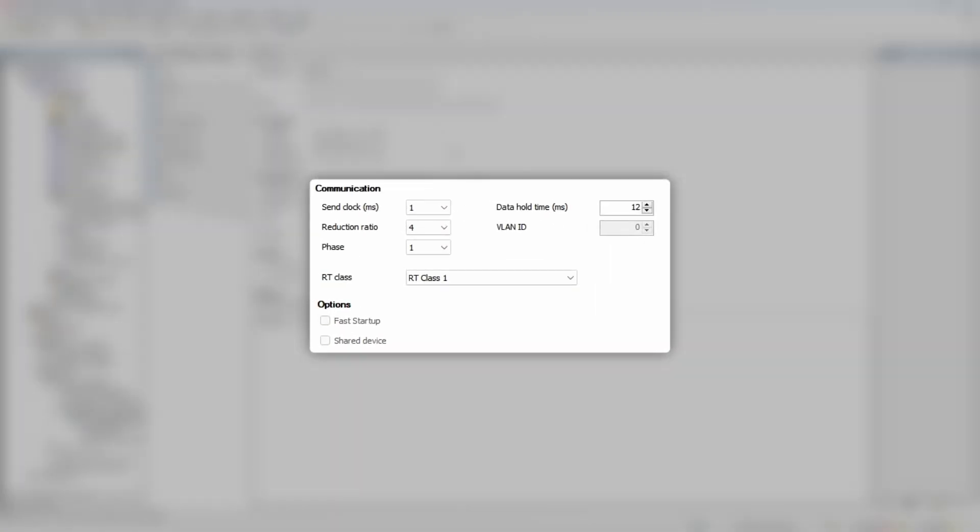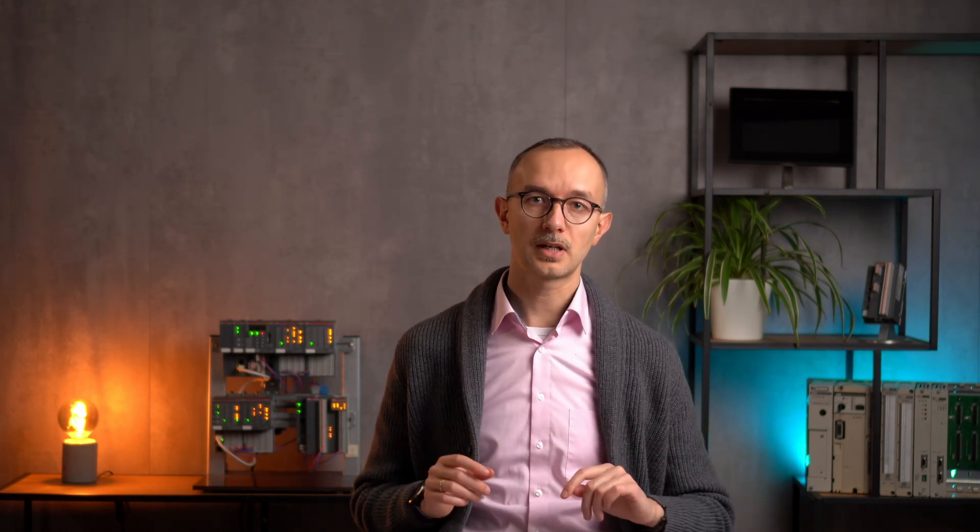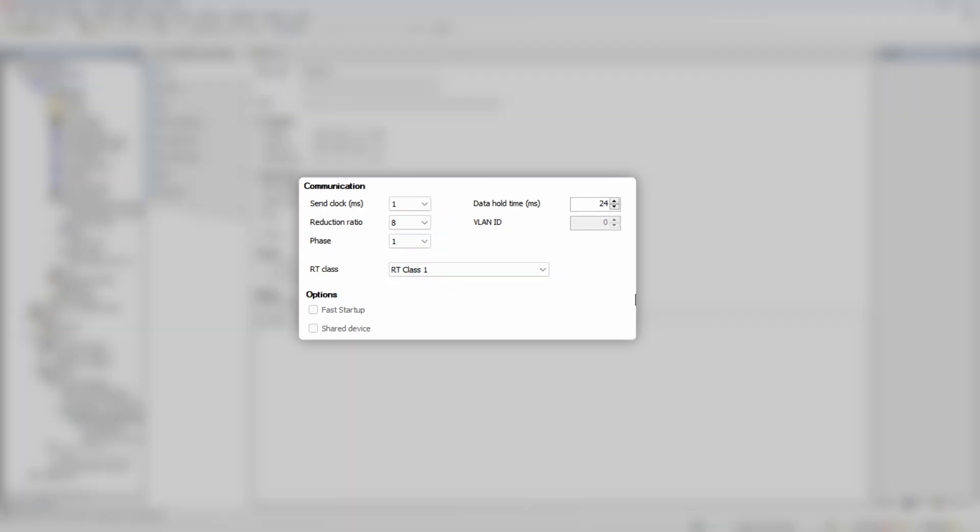Parameters under communication section define how often PROFINET controller reads inputs from and writes outputs to the I.O. device. With send clock parameter set to 1 ms and reduction ratio set to 4, we'll get 4 ms cycle time. If you remember, PLC's main cycle time is 10 ms, which means that local I.O. channels are updated every 10 ms, so we can easily increase reduction ratio to 8 to save some network traffic.